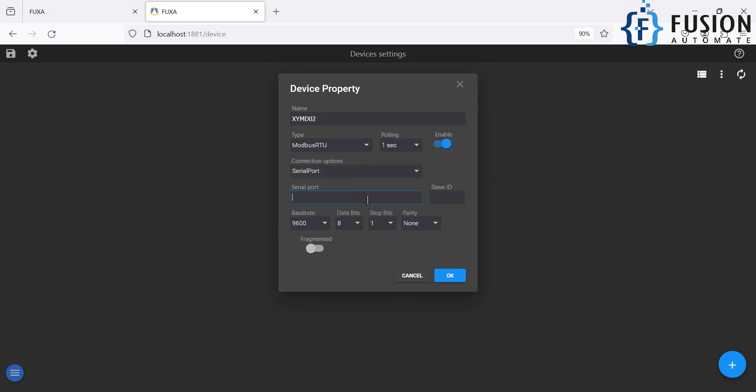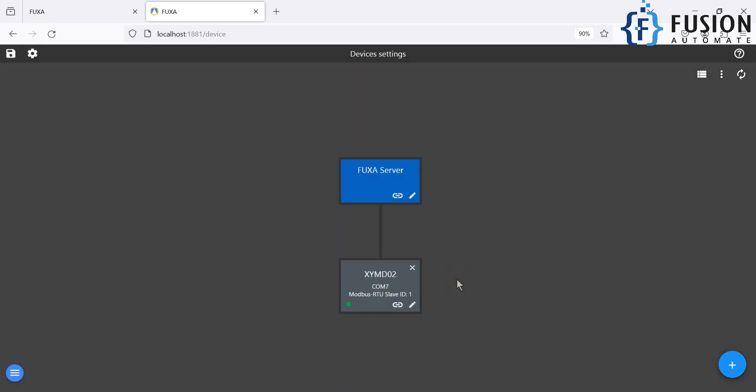The serial port is COM7, so COM in the capital, 7 is the number. And slave ID is 1. And here is the serial parameter: baud rate 9600, data bit 8, stop bit 1, and the parity none. And then after you have to press OK. And if you see the green light, then everything is good. We are able to create the tags. And once we create a tag, we will get the data.